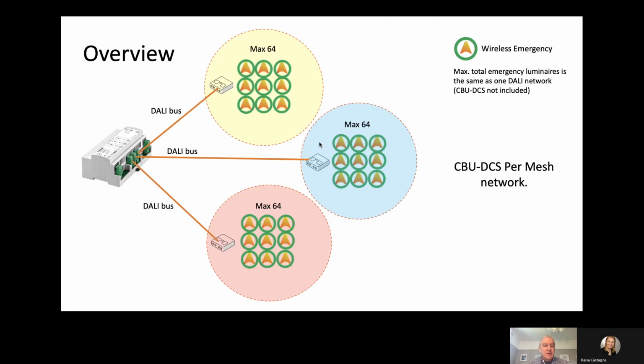So looking into the solution in a bit more detail, as an overview, you can have this topology where you would have 3 separate Casambi mesh networks. In each network, you can have up to 64 emergency luminaires that are Casambi enabled, and you have one additional node, which is the DCS module in the same network. The DCS module doesn't appear as a DALI device, so you can use the maximum of 64 for 64 luminaires, and the communication back to the controller would be a DALI bus. We feel that on a lot of occasions, the DALI bus will be a very short piece of cable, maybe only centimetres long, which would mean that the DCS modules are within the same location or even in the same enclosure as the DALI controller, SceneCom.